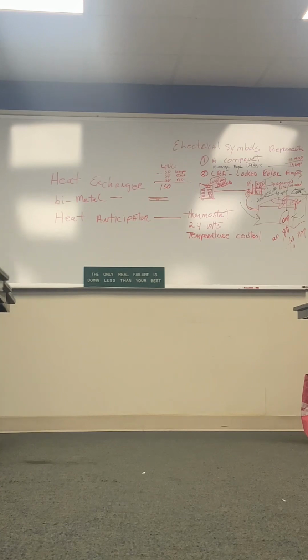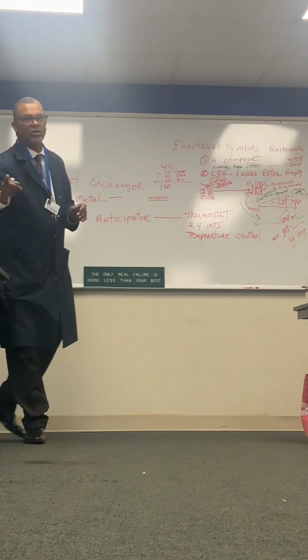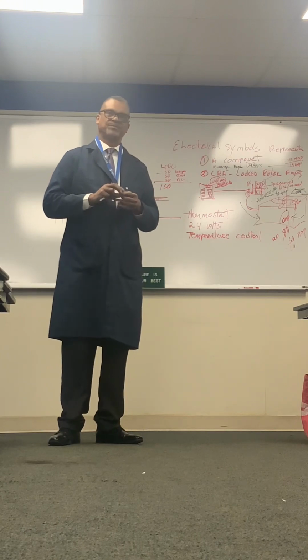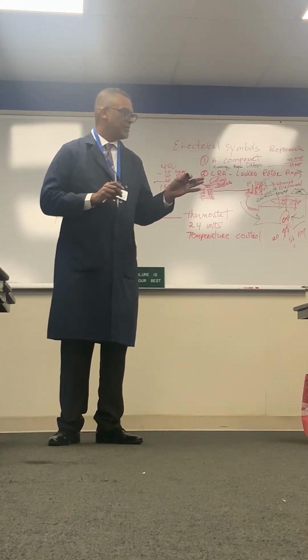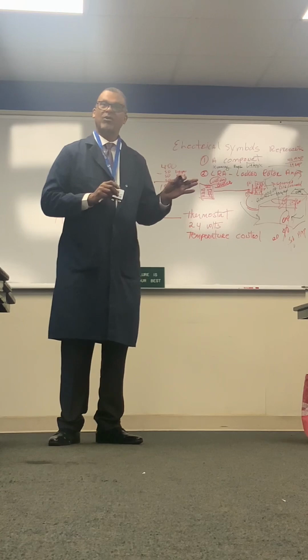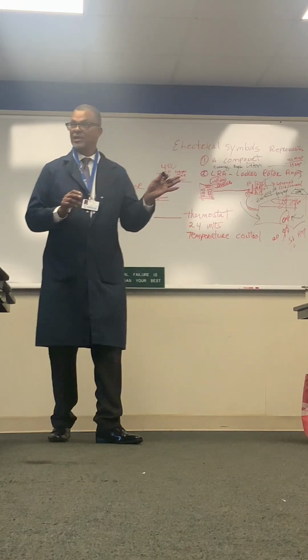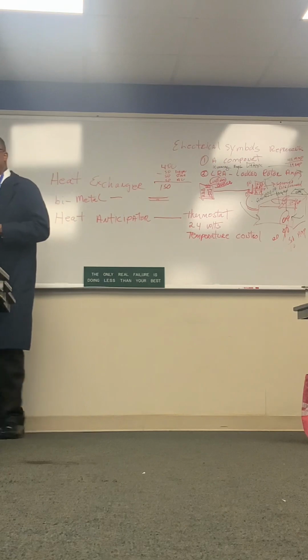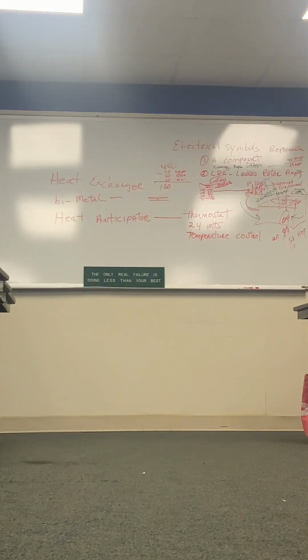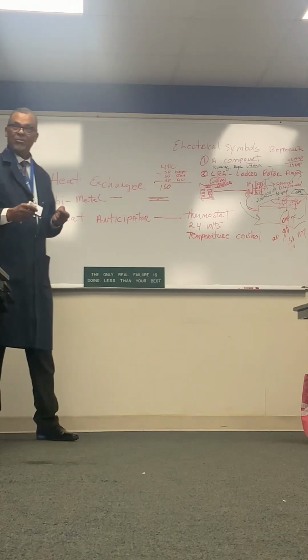So you have to get used to knowing the components. What do I look at first? The first thing you look at, I know you know this, is what? Oh, thermostat. Is it on both? Voltage. Voltage outside, if I'm on air condition, and I wanna see if I have 240 outside, where? Cut off breaker. Cut off switch. At the disconnect. See, we're gonna be talking, we're gonna say disconnect. But it could be a circuit breaker in the disconnect. But it's at, or you could test it somewhere else on that unit, where?